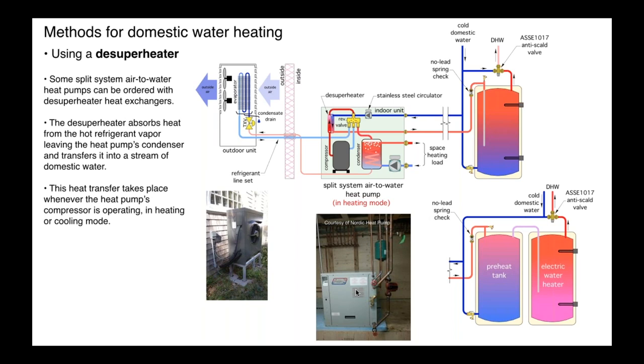And of course, this is the indoor unit, so we don't have to be concerned about it freezing on the inside. Some of the heat pump installers prefer to go to two tanks on a de-superheater. This is something that's kind of evolved in the geothermal heat pump market. The idea is that the preheat tank would stay at a lower temperature and allow more BTUs to be captured from the de-superheater. And then as hot water is drawn at the fixtures, that preheated water goes in and gets a final boost from the elements in the tank.